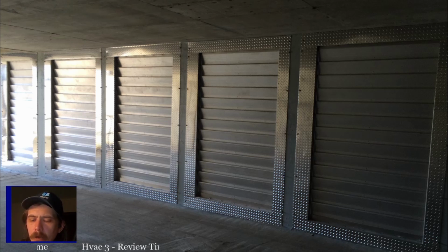failed, whether it be a mechanical failure or an electronic failure, whether in the motor control section or in the motor section itself, so that you understand what the failure was, so that you can try and look for problems that may prevent it in the future, whether it was a voltage surge that hurt the motor control section or was a bearing failure. So typically not a whole lot you can do about those, but you can pay attention to the operating conditions of the bearings and what type of bearings are in it and all that. So that's the quick overview on ECMs real quick.